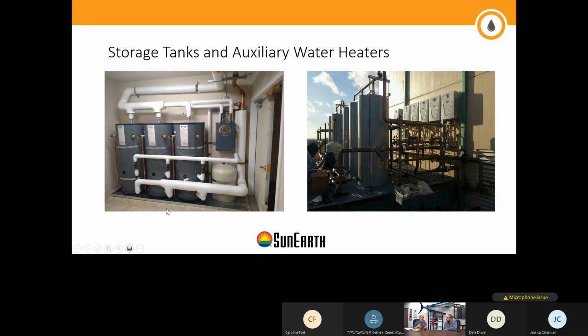Because some rooms are converted, they may have an empty storeroom. On the ground floor, is there a drain there? If there isn't a drain, are you going to waterproof that entire room in order to prevent water from going under the sill plates and into living spaces? So a lot of things that you have to consider. Also, fire penetrations. If you're penetrating firewalls, you have to make sure you use the right fire caulk and seal all the pipe penetrations, or electrical pipe, any kind of penetration through the wall, to fire code. That's a building code, but again, fire. All that retrofit is a lot of details you've got to cover.